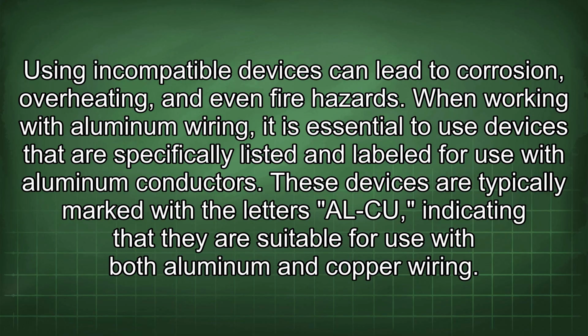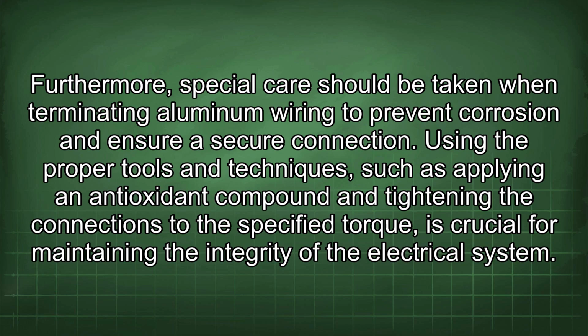aluminum and copper wiring. Furthermore, special care should be taken when terminating aluminum wiring to prevent corrosion and ensure a secure connection. Using the proper tools and techniques, such as applying an antioxidant compound and tightening the connections to the specified torque, is crucial for maintaining the integrity of the electrical system.